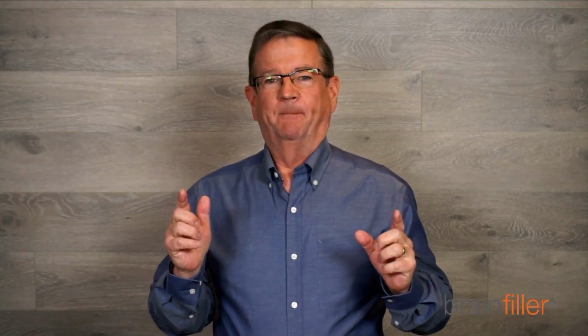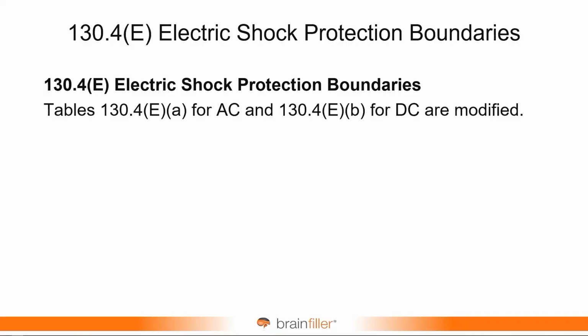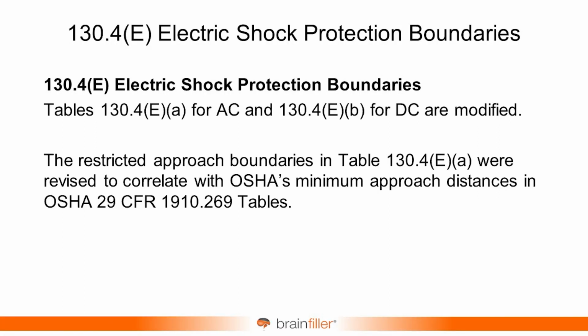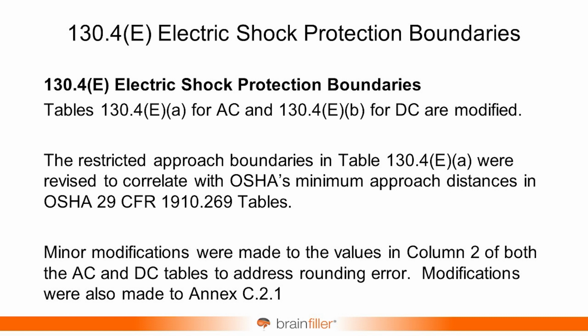One of the modifications is the restricted approach boundary. And I would get this question a lot, that OSHA has what are referred to as minimum approach distances, which are pretty similar to the restricted approach boundary, similar intent, similar meaning, but the numbers were a little bit different. And it was always, why is that? So there was a modification to the shock boundary tables, table 130.4(E)(a) and (b) for both AC and DC tables. The restricted approach boundaries were revised for the AC table to correlate with OSHA's minimum approach distances. And there were some minor modifications in column 2. That is the limited approach boundary for movable conductors. And that was to address rounding error.